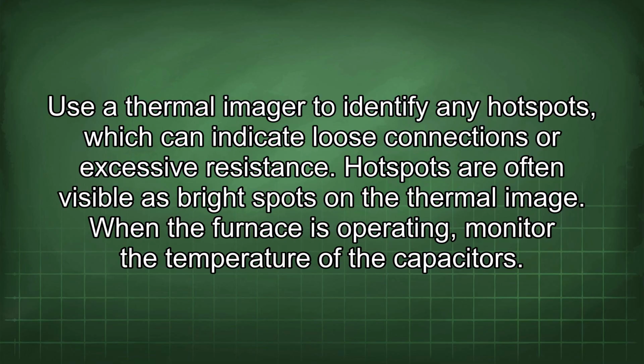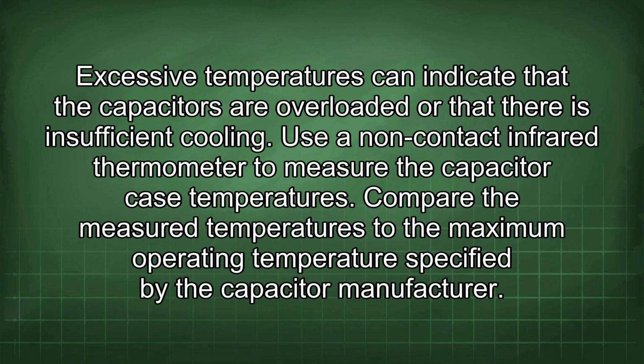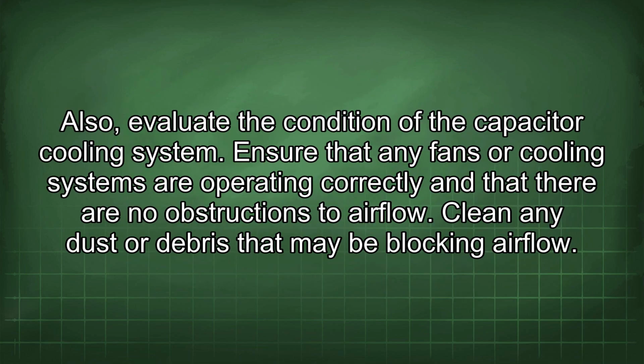When the furnace is operating, monitor the temperature of the capacitors. Excessive temperatures can indicate that the capacitors are overloaded or that there is insufficient cooling. Use a non-contact infrared thermometer to measure the capacitor case temperatures. Compare the measured temperatures to the maximum operating temperature specified by the capacitor manufacturer. Also, evaluate the condition of the capacitor cooling system.